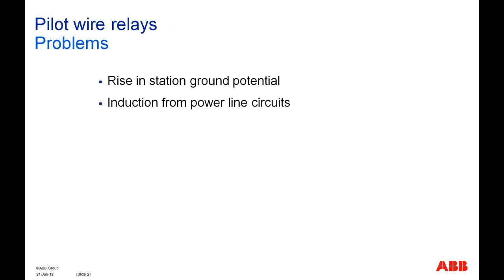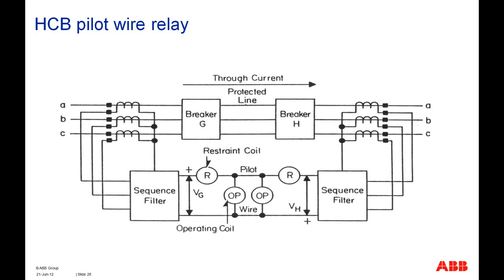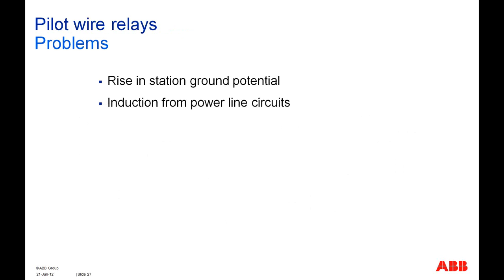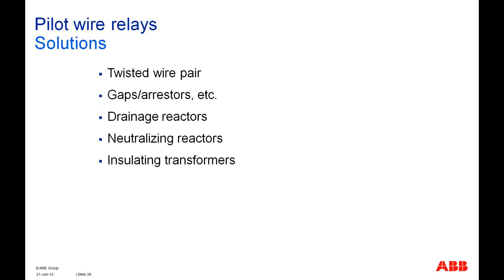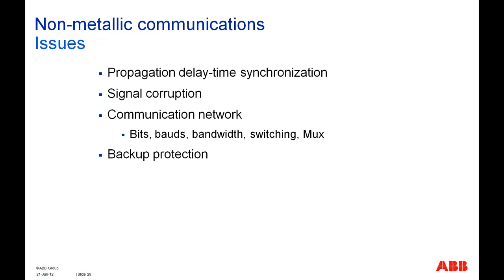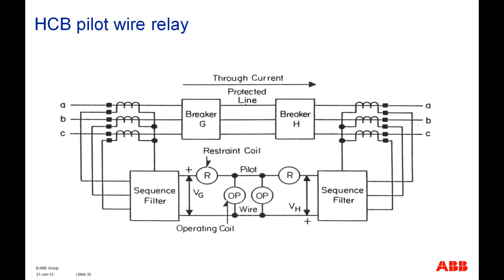But there were some problems associated with the pilot wire use in these schemes, and those were related to the station ground potential rise, as well as induction from the power line circuits. Because of those problems, we were having troubles and maloperations in the pilot wire protection schemes. And those maloperations were basically that if, for example, somehow the pilot wire breaks in some area, or there is a break happening in the pilot wire.